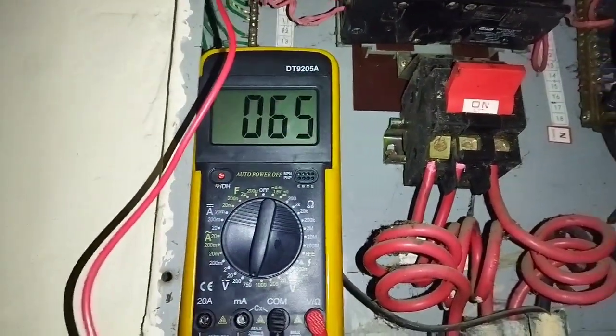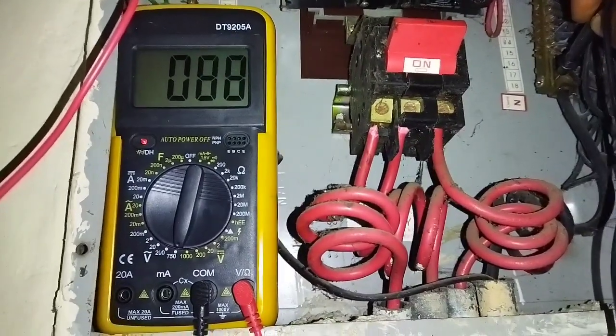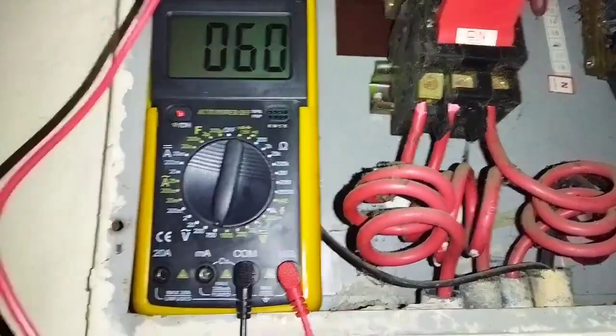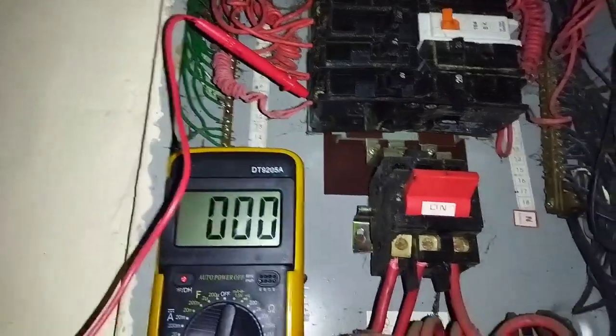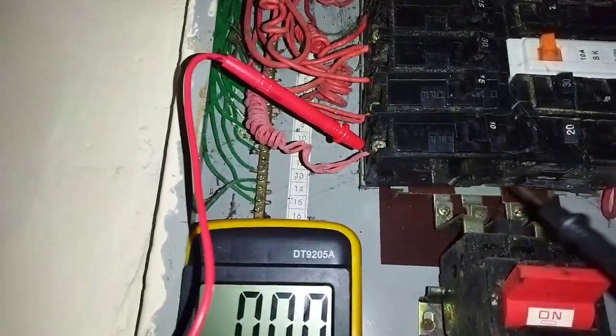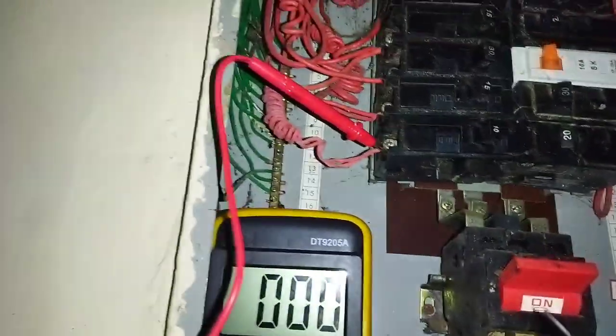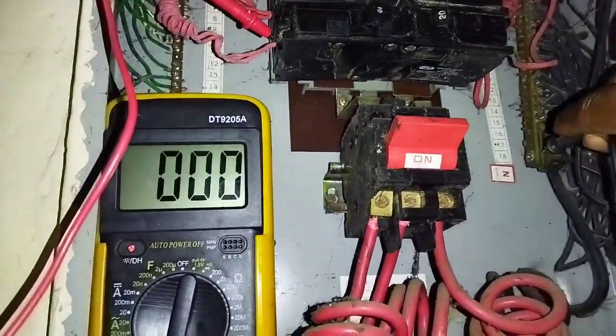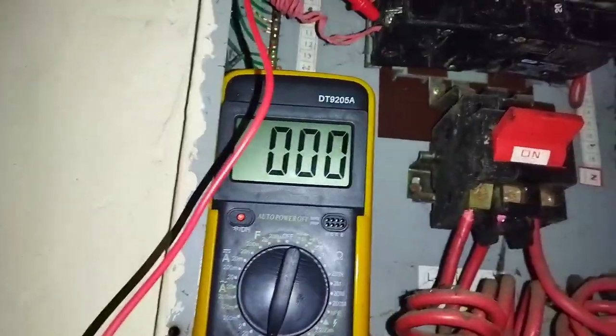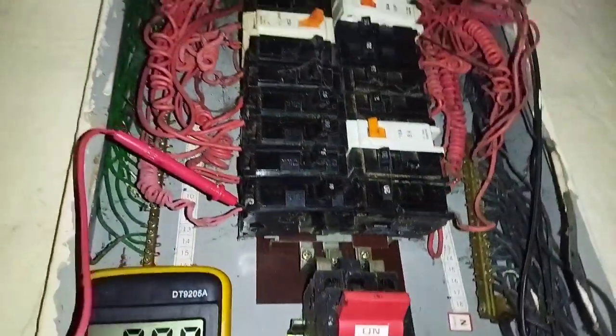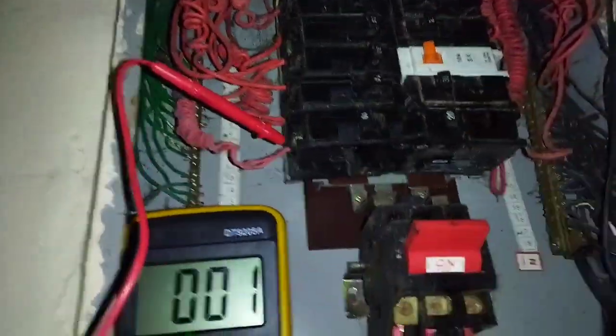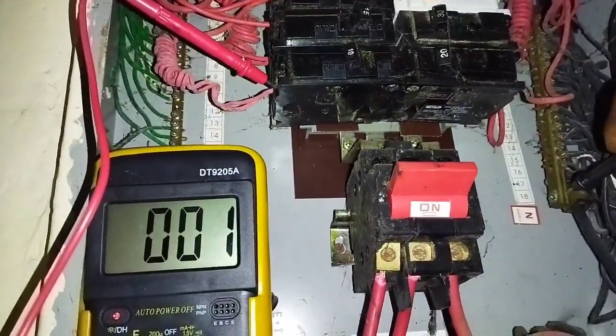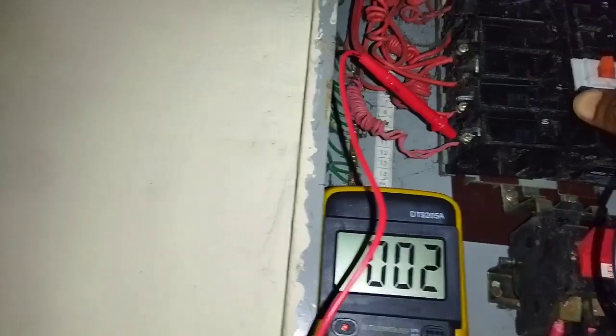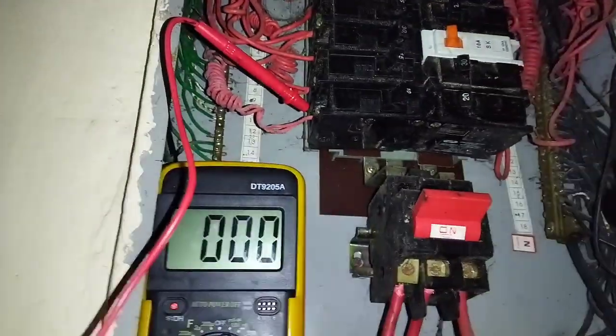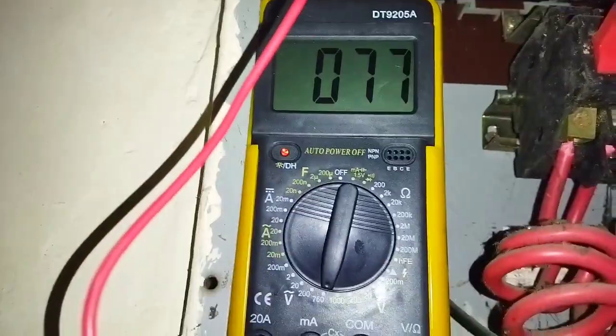Good. So we are having 65 volts AC. It's actually varying, but it shows that this breaker is working. Sometimes a breaker can be faulty but still remain at the on state. To know, you test for voltage across this point and the neutral point. If you don't get any voltage reading, then you know that breaker is faulty. If it trips off, it's off right now, and if I test for voltage here, you will not get any voltage reading. If I put it back on and test, you can see we have voltage.